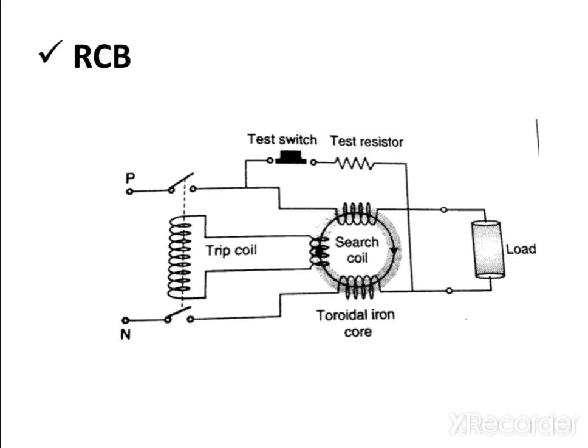Under normal operating condition, the phase current is, let's say, 5 ampere. This 5 ampere current is flowing through the search coil, through the load and toroidal iron core and neutral. So the magnitude of the fault current is 0 in this case, because the incoming current is 5 ampere and outgoing is also 5 ampere. So there is no operation of the trip coil here.